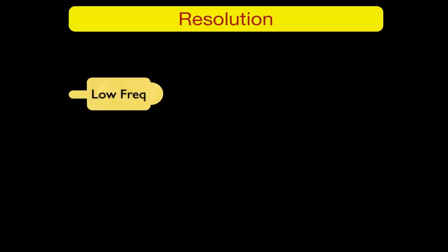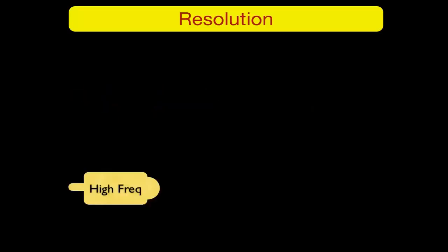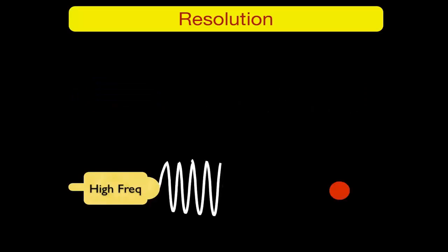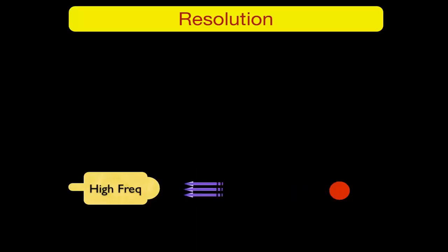One important factor is frequency. With a low frequency probe and a small object, there is a good chance the sound wave will miss that object. On the other hand, with a high frequency probe and the same small object, there is less chance of missing it, producing a reflection back to the probe so the object is displayed on screen.